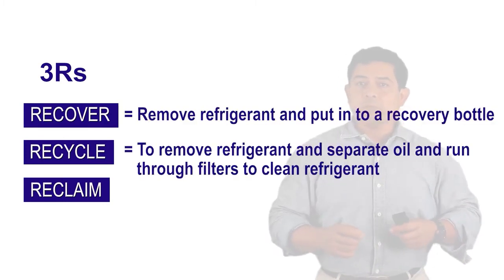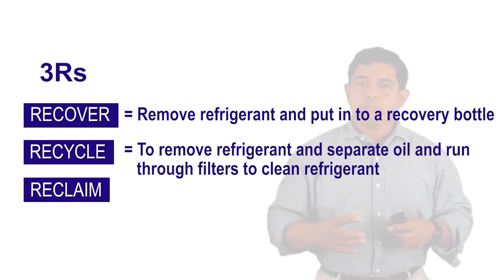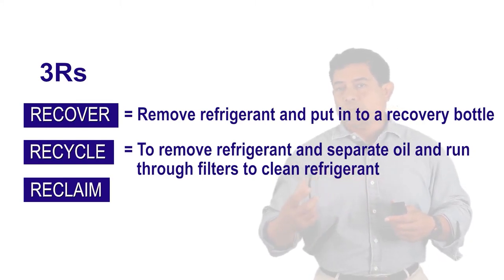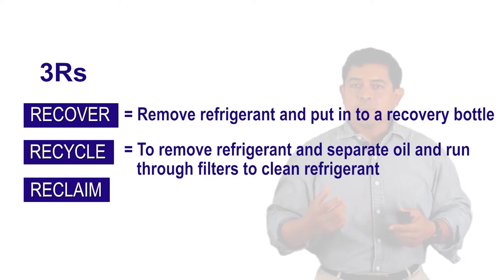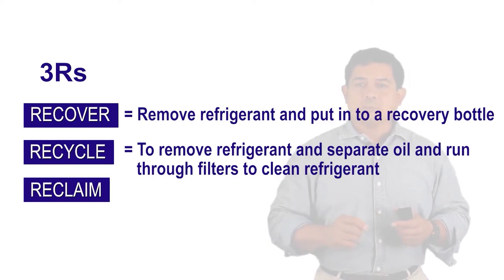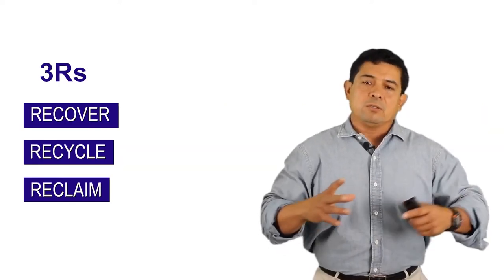To recycle, well that is to clean the refrigerant immediately right there on site by oil separation and running it through filters. The filters remove the acid, moisture that may be in it, and the oil. Then you use it again instantly to put in a machine. Now that's called recycle. You don't send it any place. You do that on site.